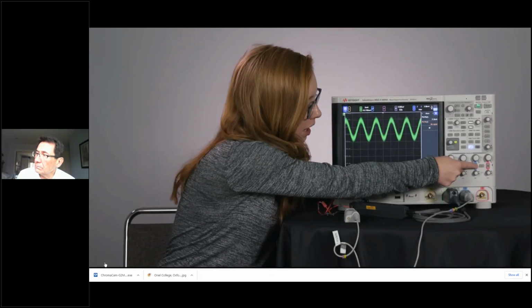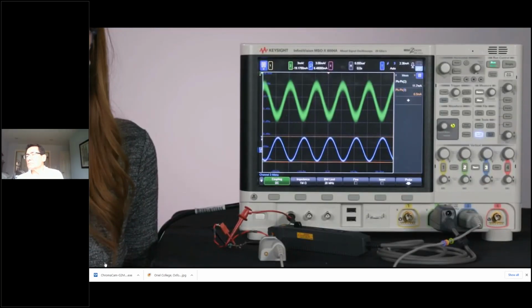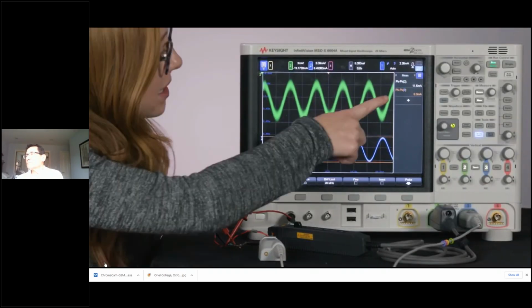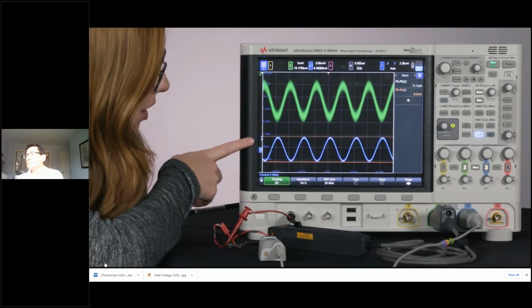So if we look at an example, on channel 2, I have that clamp-on current probe we were looking at before, and on channel 3, a high sensitivity current probe. The true signal that we're measuring is 6 milliamps, and we're getting almost exactly that with the high sensitivity current probe because there's barely any noise from the probe riding on the signal.